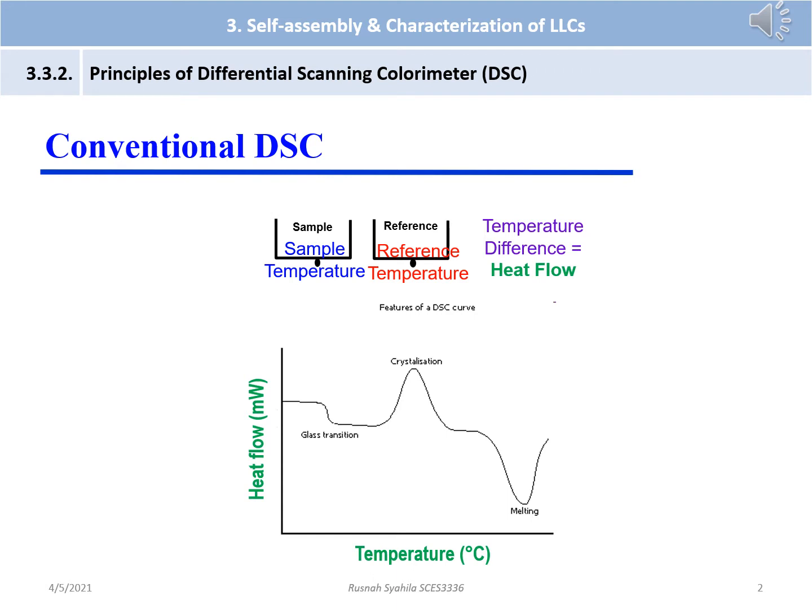The samples were cooled at a rate of minus 5 degrees Celsius per minute to minus 40 degrees Celsius, kept at minus 40 degrees Celsius for 2 minutes, and then heated to the required temperature range. When a melting or freezing transition occurs, the sample pan is cooler or hotter than the reference. Therefore, the instrument needs to supply different heat to keep temperatures the same. The difference allows the heat, the delta enthalpy, and the temperature of transition to be measured.